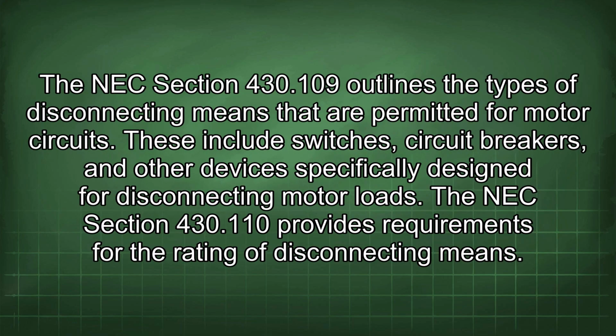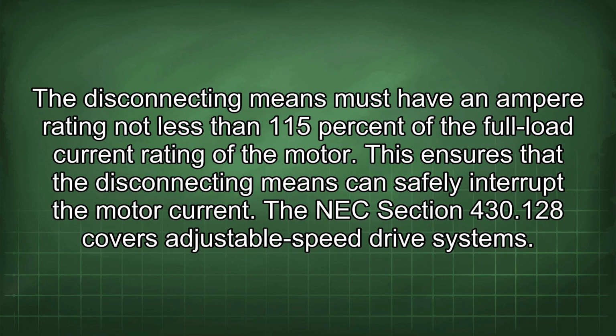The NEC Section 430.109 outlines the types of disconnecting means that are permitted for motor circuits. These include switches, circuit breakers, and other devices specifically designed for disconnecting motor loads. The NEC Section 430.110 provides requirements for the rating of disconnecting means. The disconnecting means must have an ampere rating not less than 115% of the full load current rating of the motor.